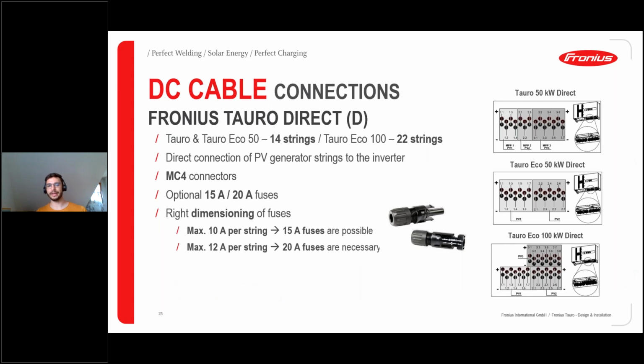Okay, now in a little bit more detail, how is it looking on the DC side on a Fronius Tauro direct variant? So we recall the direct variant means we have a decentral system topology where the product, the Tauro, is distributed across the field and installed directly to the strings of our PV arrays. And there we can see, of course, we have MC4 plugs. That's the main difference on the direct version.